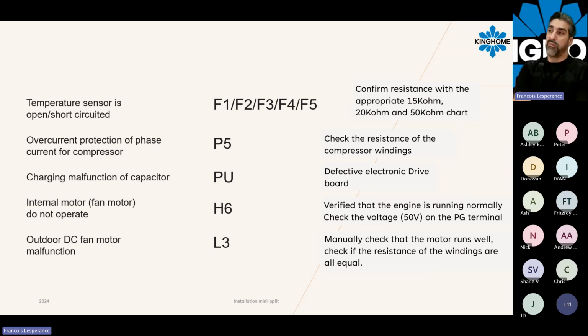Error codes F1 to F5 are related to temperature sensors. So physically, if the temperature sensor is out of range, open, or short circuit, you will have an F1 to F5 regarding which temperature probe is problematic. We use three different kinds of sensor. Return air sensor and outdoor air sensor use a 15 kilohm sensor. The liquid pipe and the evaporator tube use a 20 kilohm sensor. And the discharge sensor is the only one at 15 kilohm. So when you look up the service manual, make sure you refer to the right chart when you check the resistance of the sensor.